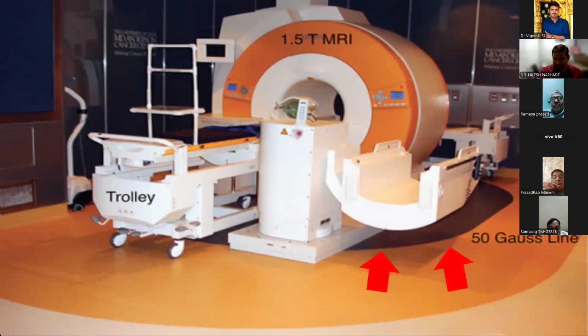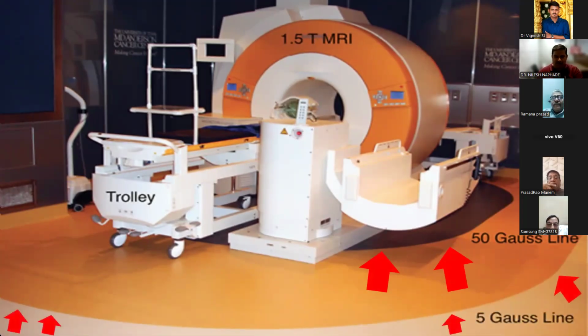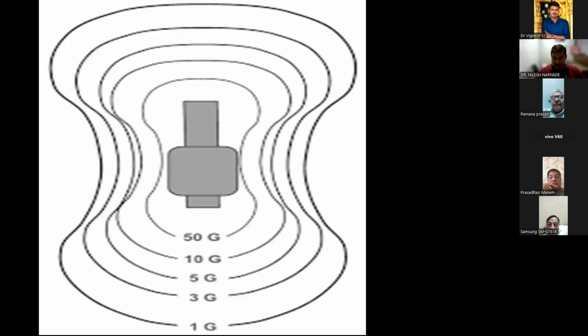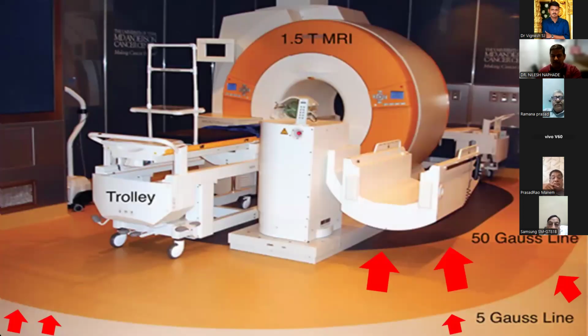What the arrows are showing, that brown thing, the border of that is called the 50 Gauss line, which means that the strength of the magnetic field within that line is 50 Gauss. A very high magnetic field acting in that area is called the 50 Gauss line. And the outer line is called the 5 Gauss line. And this 5 Gauss line is also called the pacemaker safety line.